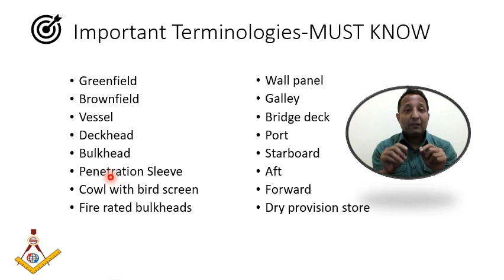SOLAS clearly defines that if any HVAC duct penetrates a fire rated bulkhead, and the size of that penetration is equal to or more than 750 square centimeters, then that bulkhead, made of steel, has to be provided with a minimum 3 mm thick mild steel sleeve, 900 mm long. It could be 200 or 700 or 450 on either side of the bulkhead, but the total length should be 900 mm. This is called a penetration sleeve. On either side of the sleeve, you continue with the ducting. Since it is penetrating the fire rated bulkhead, we need to install the penetration sleeve. This is a very common question we should remember.